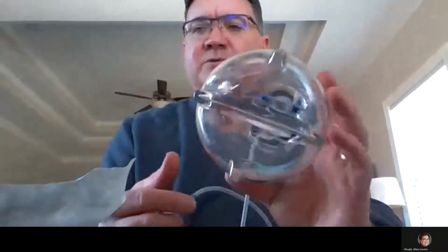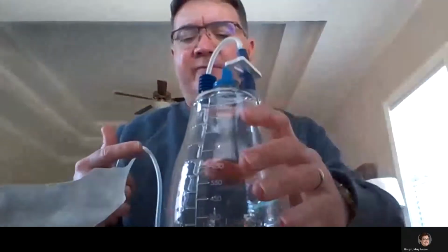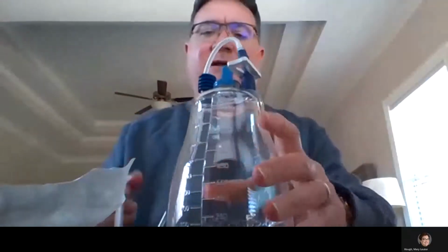We now have our extension line, which is extra, extra long. This is important because it gives the ability to keep the bottle down by the patient's side while they're sitting at their dining room table or in their Lazy Boy recliner. Because even though we are using a vacuum, gravity does help in getting a lot of that fluid out. So a couple of neat little key features that we have on here. First and foremost, unlike PleurX, we have 4 feet on the bottom here. That's to help prevent it from tipping over, which you won't find on any other bottle.